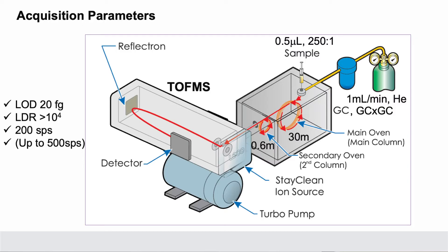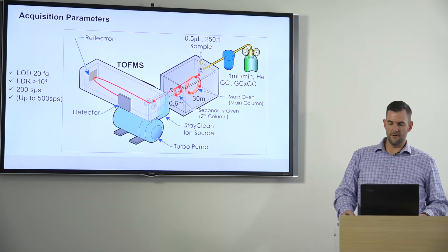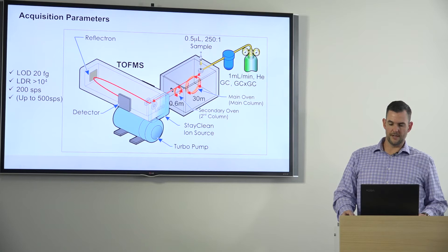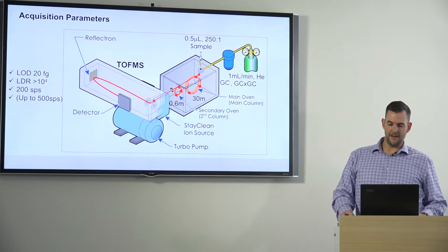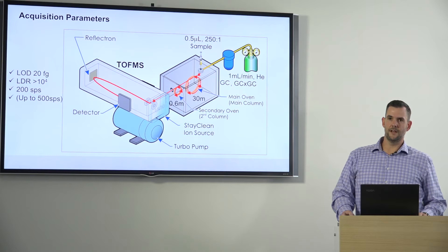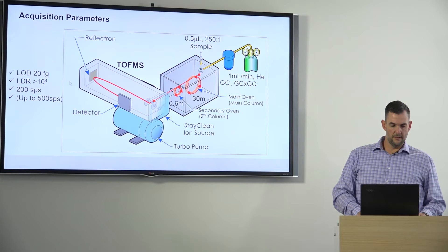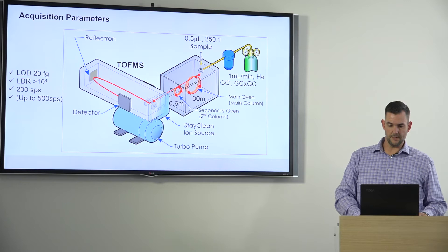Here's a cartoon that depicts how the system is made up of its different components. We have a 30-meter first dimension separation column, which is the RXi-5 — that's our primary separation — coupled with a 0.6-meter second dimension column of a different stationary phase, the RXi-17. The idea is that with different stationary phases, we'll be able to separate analytes that may not have separated effectively on the first dimension. Limits of detection achievable on this system are 20 femtograms, linear dynamic range greater than 10⁴, and the instrument is capable of up to 500 spectra per second.